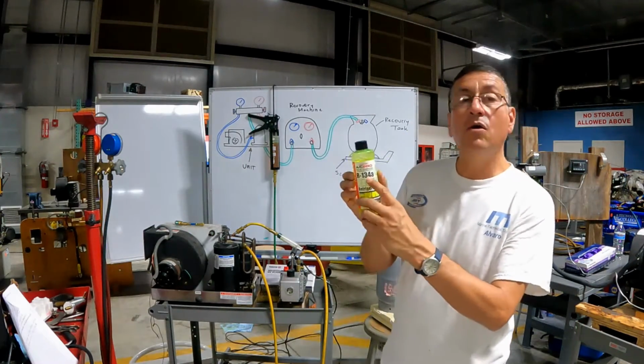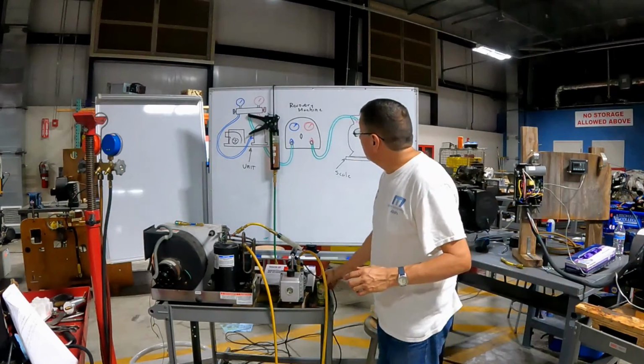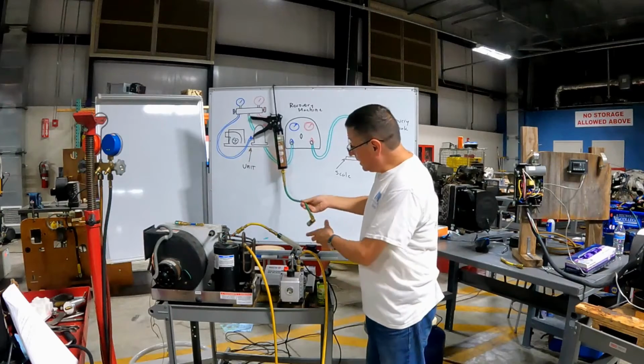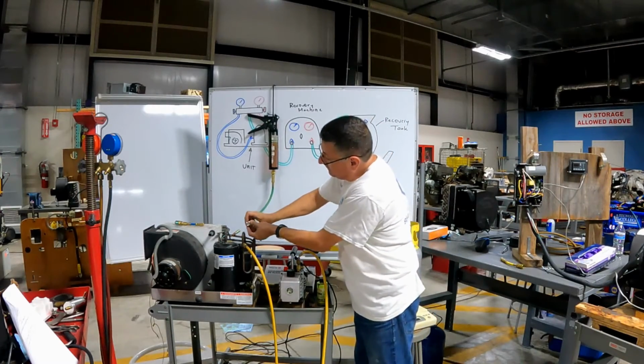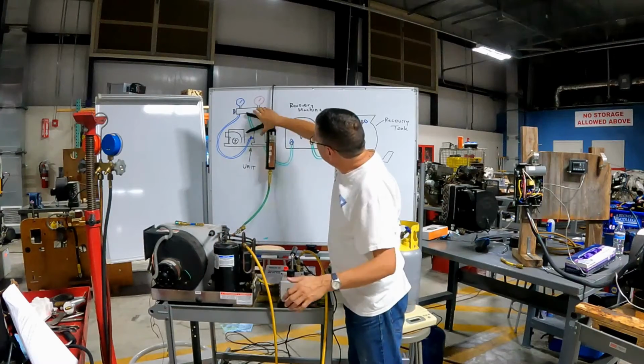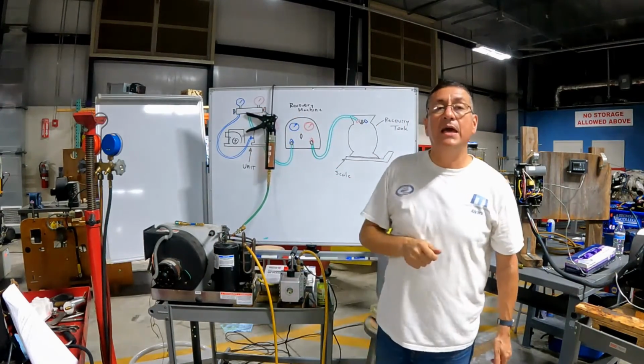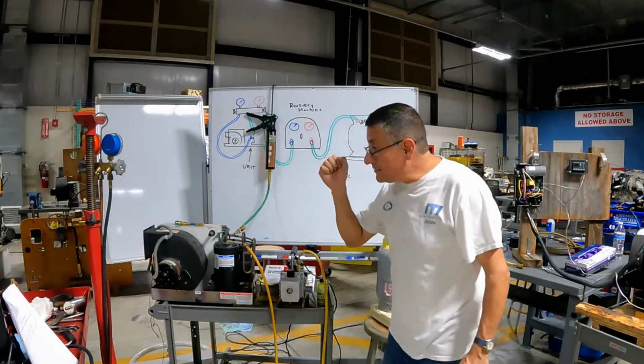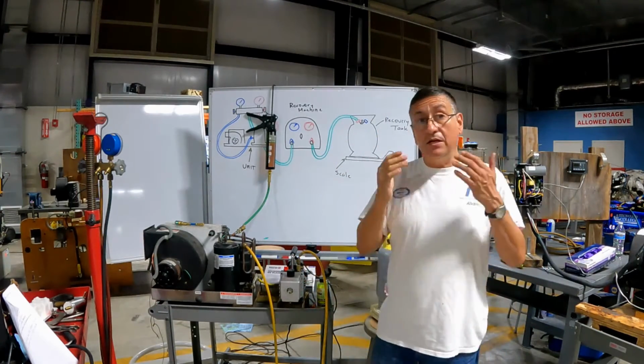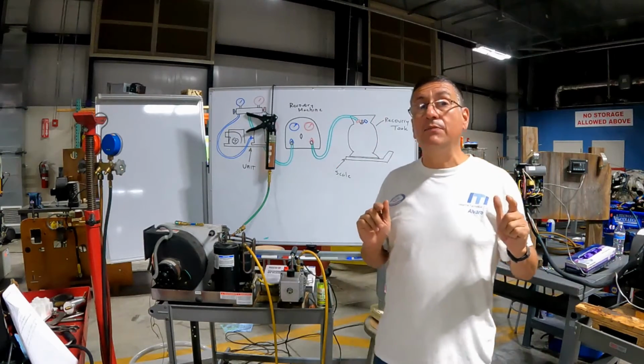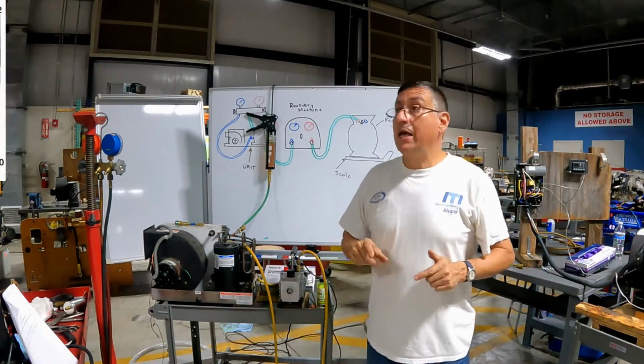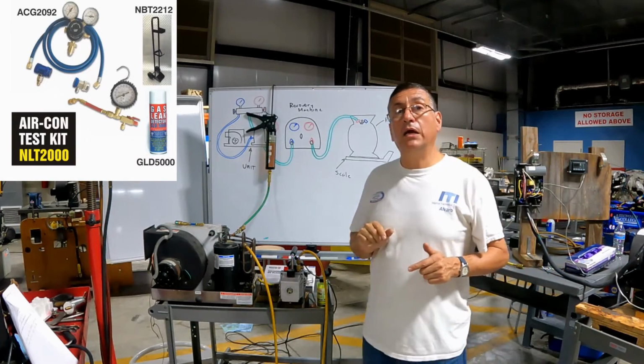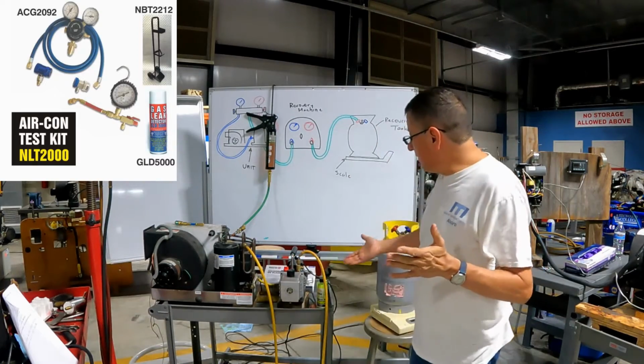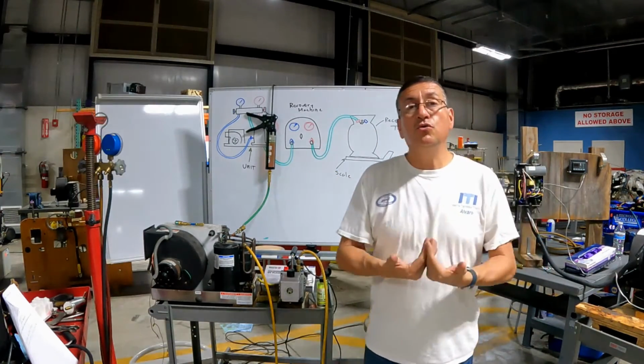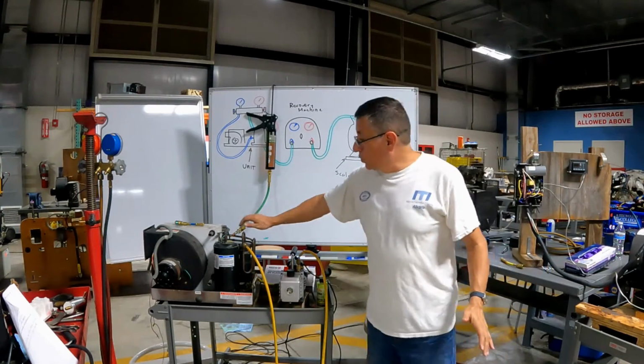This one is for R134A, but there are other ones for R410, and they have the fitting, the adapter, to connect to the system, and right then you introduce the dye. After that, with the flashlight, it's easy to identify where the leak is. This is a simple way, or you can pressurize the system with dry nitrogen, in a canister like this, which is a perfect way to identify if you have leaks. But with the dye, it's too simple. I recommend using the dye. It's a simple way to do that process.